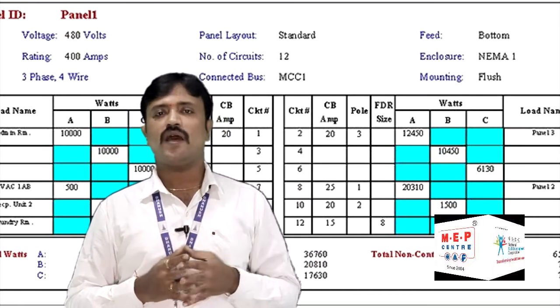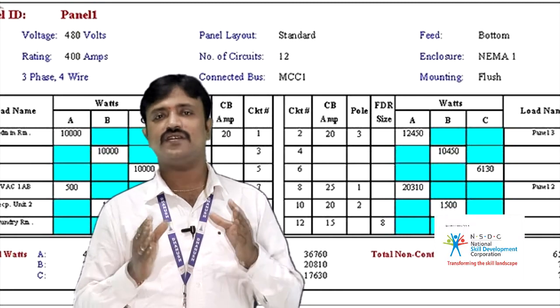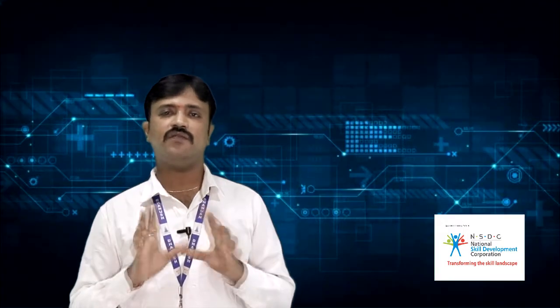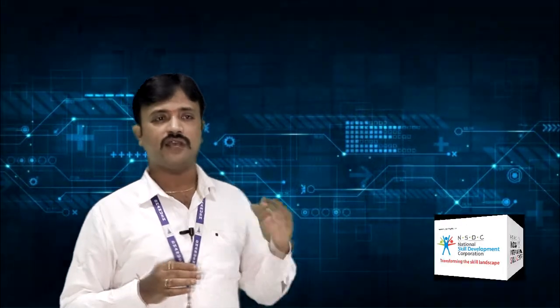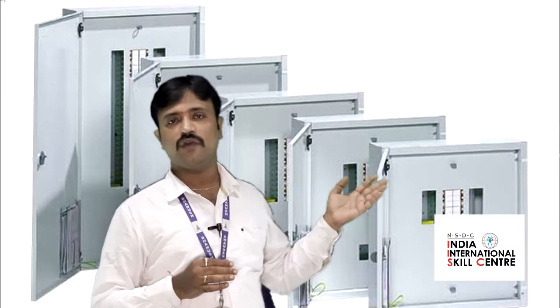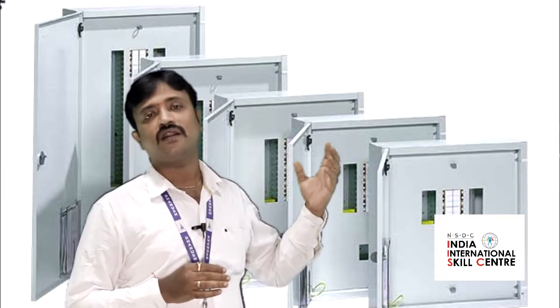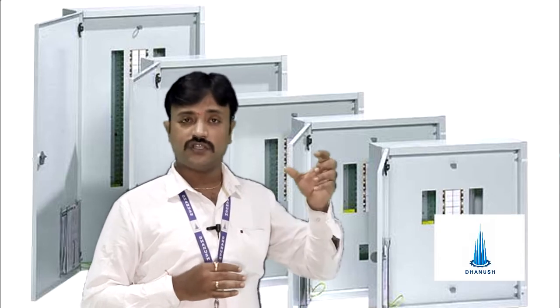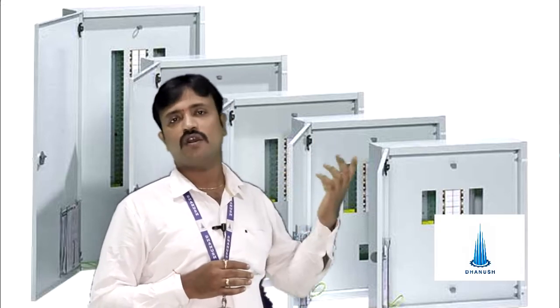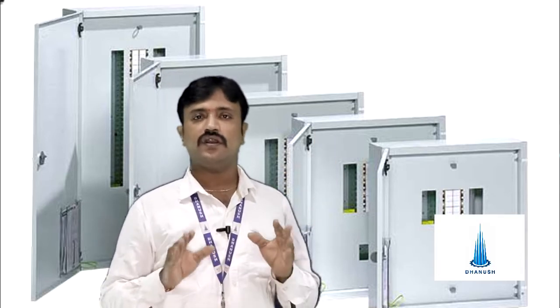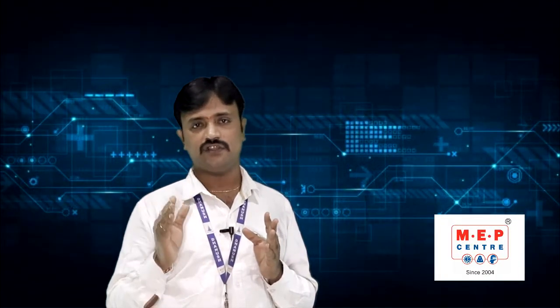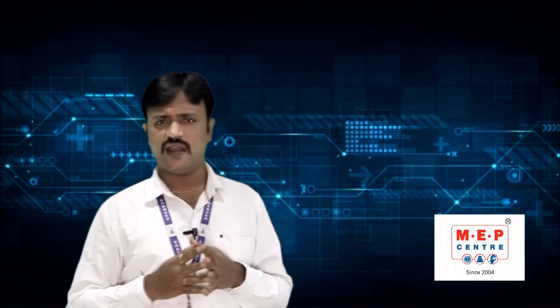By doing the load balancing sheet, we'll get the size of the distribution board. What is the size of the DB we require, whether it's a 2-way DB or 4-way? As you can see in the images, we have a 2-way DB, 4-way DB, 6-way DB. Likewise, we need to calculate the size of the distribution board, and what the incomer circuit breaker size is and what the outgoing circuit breaker size is. So we are going to get the size of the DB, and the load should be equally balanced across the three phases, that is R phase, Y phase, B phase. This is about the load balancing sheet.